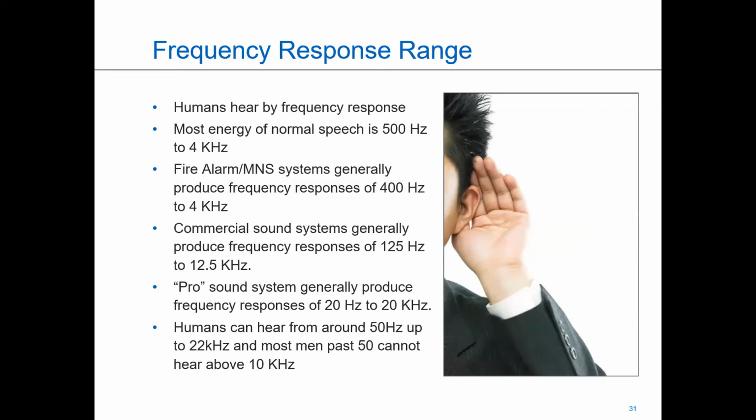Frequency response. I said earlier, I use a lot of speakers and I tap them low, and I use a good speaker. Very important is the frequency response of the speaker. The normal fire speaker has changed over the years. Our speaker products, for example, even before the acquisition and the change of our products in Eaton, we were already moving to more intelligent speakers, with a broader frequency response, something that goes over a much wider range to be able to capture the speaking voice, because that's really what it's all about. So the broader the frequency response of the speaker, the cleaner that sound is.